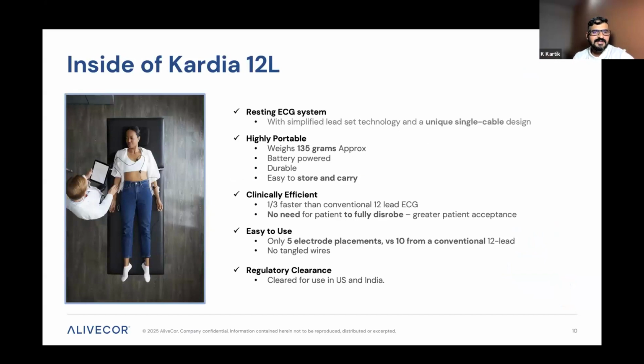Now, what does the inside of Kardia 12L consist of? It's firstly a resting ECG system, which has a very simplified lead set technology. And the USP of this device is the unique single cable design. If you see, it starts from here, goes here, and ends here, just a single cable. And the module is here. The module weighs approximately 135 grams, and it is battery operated, so there is no electrical dependency. It is highly durable. We have done durability tests as well. And the way it is made, it is easy to store and carry in a briefcase.